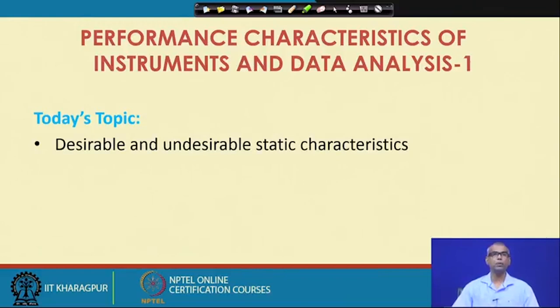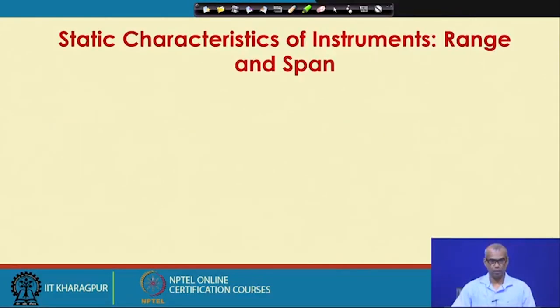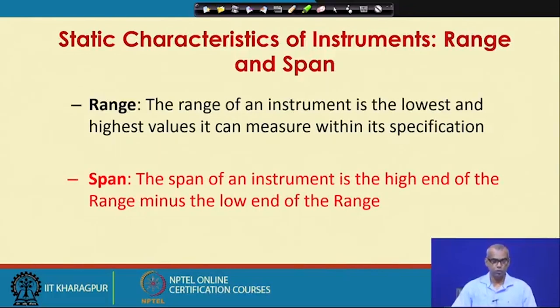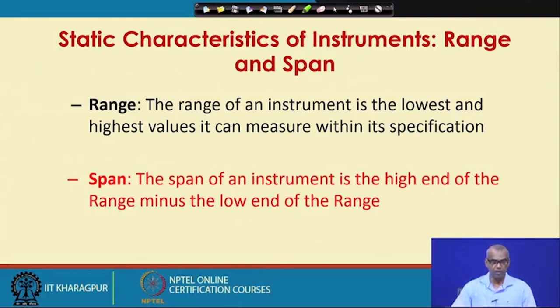Today's topic is Desirable and Undesirable Static Characteristics. There are various static characteristics, and we will go through them one by one. First, let us talk about two terms: range and span of instruments. The range of an instrument is the lowest and highest value it can measure within its specification. The span is the high end of the range minus the low end of the range — the difference between these two values.